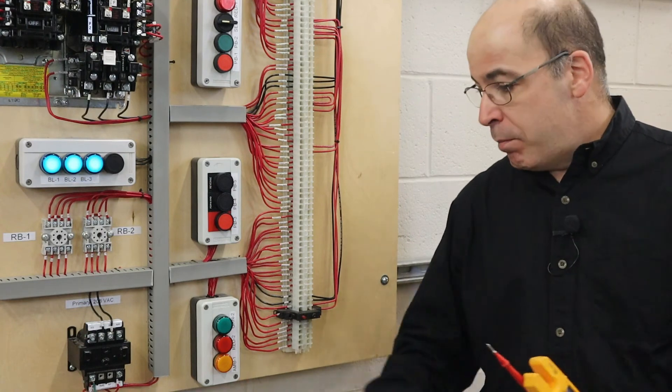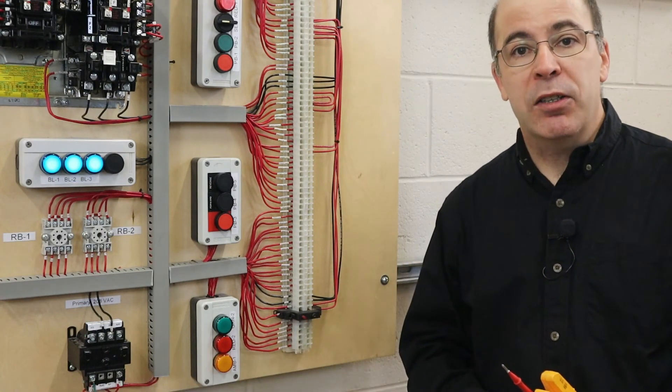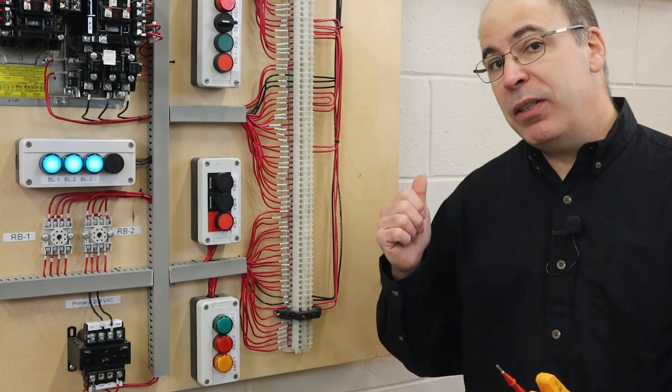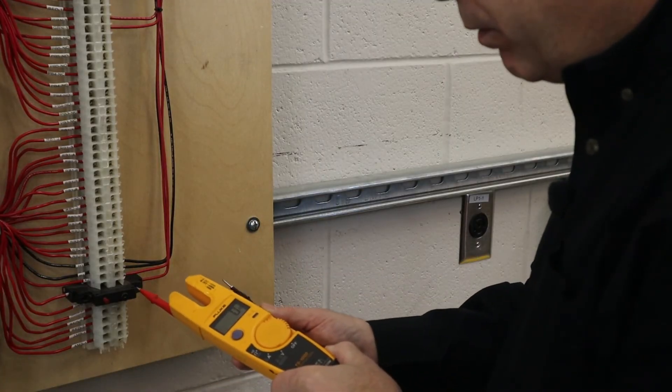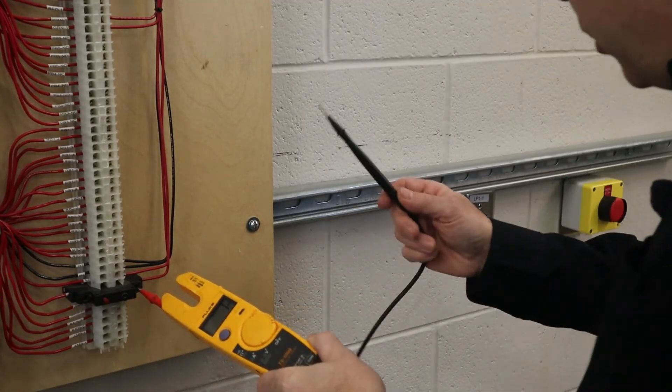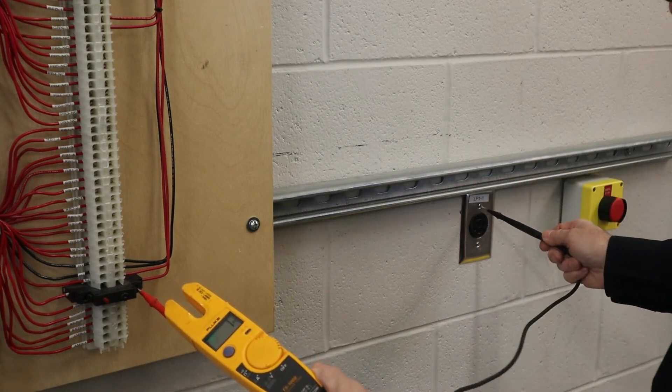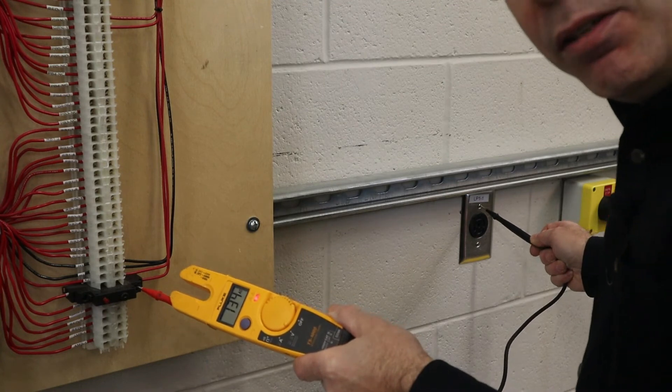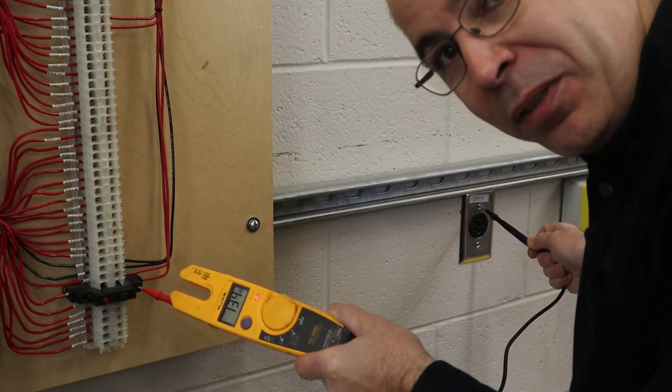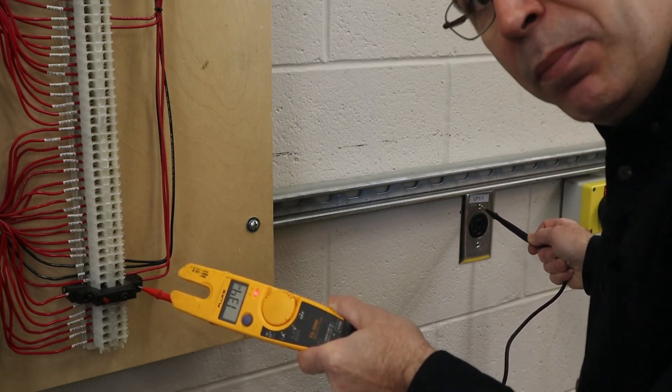But I can tell you what is bonded, and that is the faceplate of this receptacle. Because now that we've bonded the secondary of our transformer, I should be able to get a reading off of this. So we're going to take a reading from the output of my circuit breaker to the metal of this faceplate. And look, we're seeing 134 volts, which is exactly what we would hope to see.